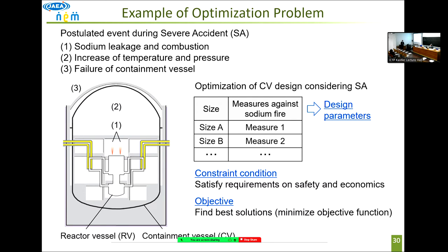Fortunately, because of the low pressure systems, even in case of a direct leak of the liquid sodium itself, it does not influence the pressure increase in the containment vessel dramatically. On the other hand, if the containment vessel is occupied by air, sodium fire happens, and surely the pressure increases. And in general, firstly, we make the containment building.